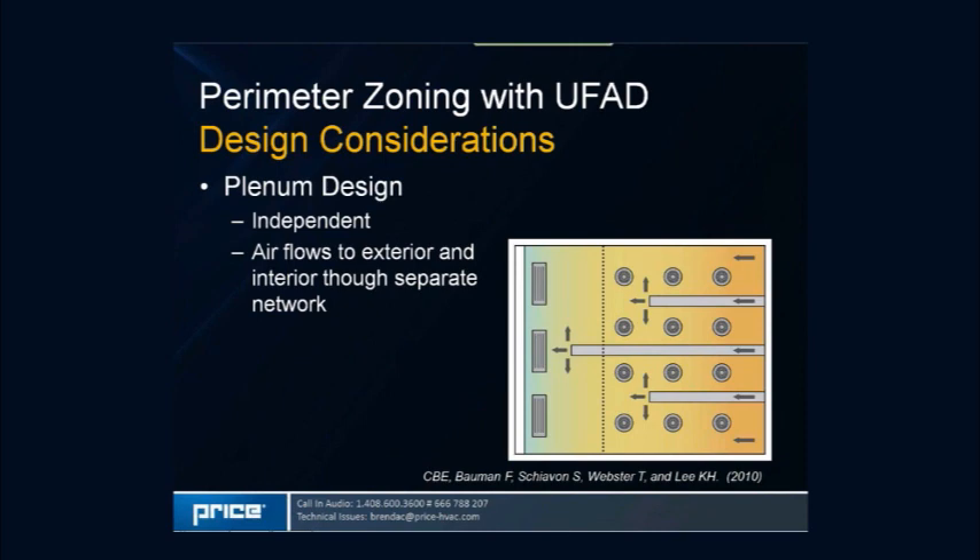The most effective design — the Cadillac system — is independent duct delivery, where a physical or non-physical separation combines the reverse series and series designs: ductwork extended right to the perimeter and also stubbed out to the central interior zone. This provides the most constant temperature across the floor plate, ensuring even conditioning to the perimeter as well as the interior zones. This is especially helpful in buildings with high equipment loads such as call centers, where interior sensible load may be as high as at the perimeter.